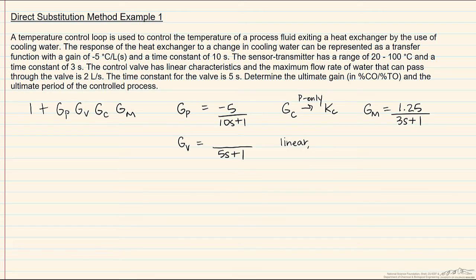We know that the valve is linear. We're going to assume in this analysis that delta P is a constant. The final part we have to figure out here is if it's failed open or failed closed. In the case of a safety issue we would definitely want cold water flowing through the process, particularly in the heat exchanger where it becomes in contact with a hot process fluid. So therefore we're going to want this valve to fail open. The importance of the fact that we're saying that it fails open is that it dictates by convention that the sign is negative. So for a linear valve with a constant pressure drop, the magnitude of the gain is simply the max flow rate over a hundred. It's a hundred because controller output ranges from zero percent to a hundred percent. So here we'll have two over a hundred, or .02.